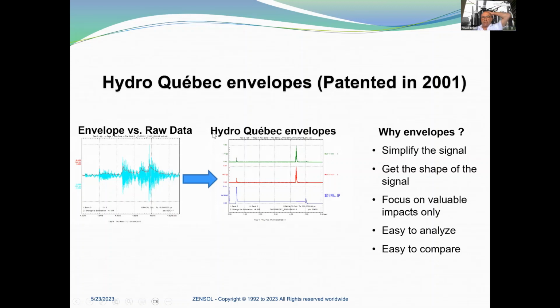So we use the Hydro-Quebec envelopes. This method was patented in 2001. Here on the left, you can see the raw data in blue, and what we call the envelope, which is calculated thanks to the software and the specific proprietary algorithm from Hydro-Quebec. So here you can see the envelope. And in fact, we have the motor current envelope that you can see at the bottom here. And here, this is the high frequency envelope and the low frequency envelope.